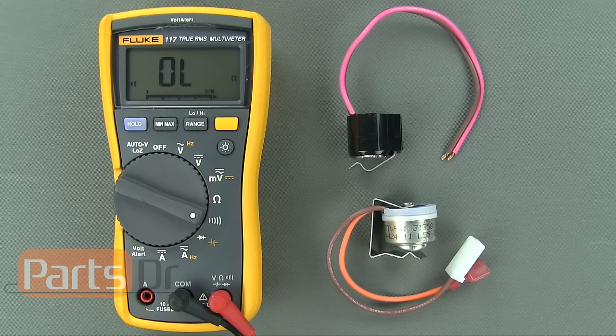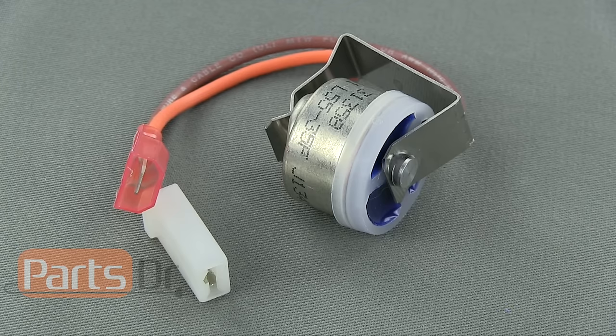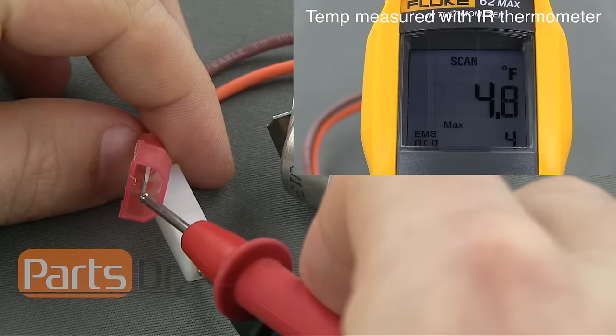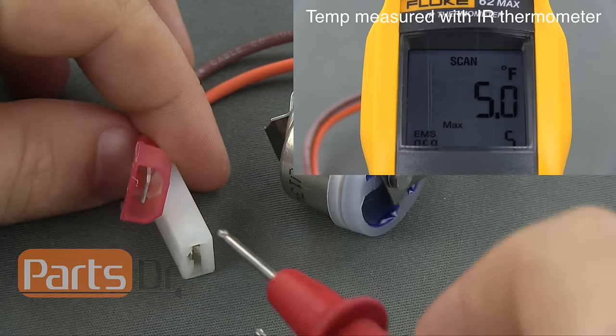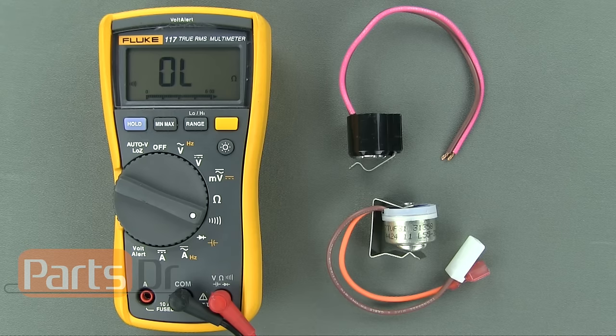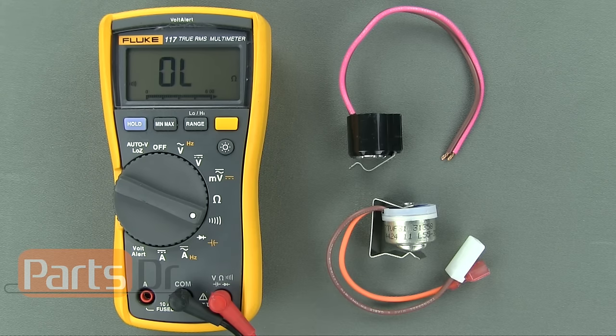Place one of each of the meter's probes on each of the defrost thermostat's wires. While the thermostat is colder than the closing temperature, the thermostat should have continuity and the meter will produce an audible beeping noise. In this case, this thermostat should be 20 degrees Fahrenheit or colder to have continuity.